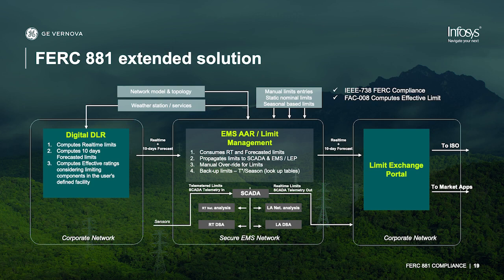It also is going to compute your 10-day forecasting, and it also allows you to be future-proof compliant with FERC in case they decide to go to a full dynamic line rating mandate in the future. And then our limit exchange portal allows you to ensure that your transmission owners and your ISOs are all operating to the same ratings by transmitting your real-time ratings back and forth between your EMSs and market systems, as well as your forecasted ratings. And then it also acts as the repository for any future audits or data interrogation.